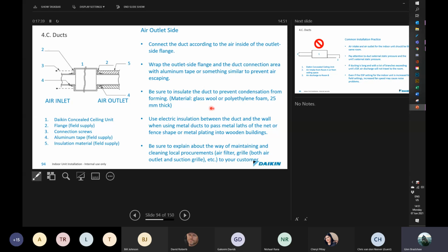Use glass wool or polyurethane foam, 25mm thick minimum. Some environments might even need 50mm. Use electrical insulation between the duct and the wall when using metal ducts. It also helps to remember to provide an earth to your ducting. And be sure to explain to your customer the way of maintaining and cleaning the locally procured air filter and grills.